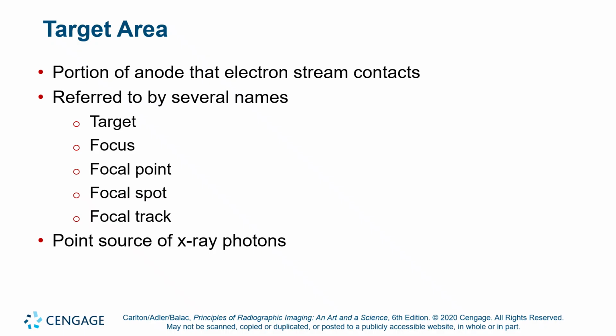Okay. The track is only on rotating anodes. A stationary anode does not have a focal track. The track is the total area: if you take the focal spot at every point along the rotating anode, then you end up with the focal track. And so the focal track is circular. The focal spot is effectively a rectangle.